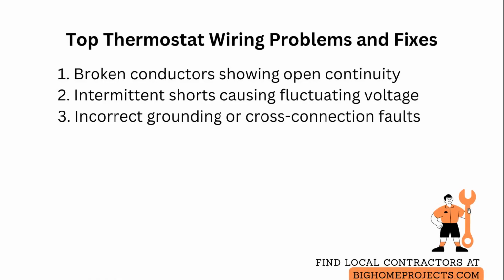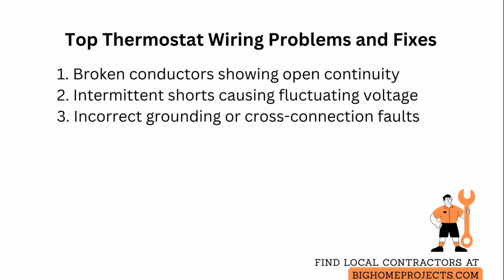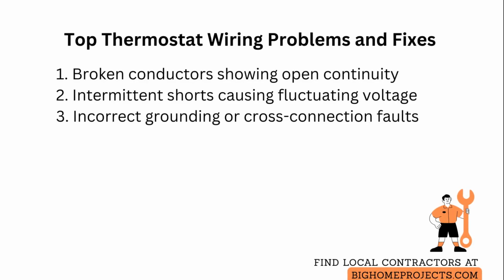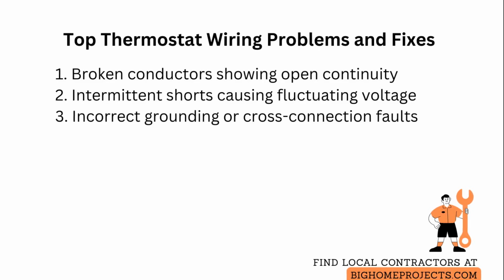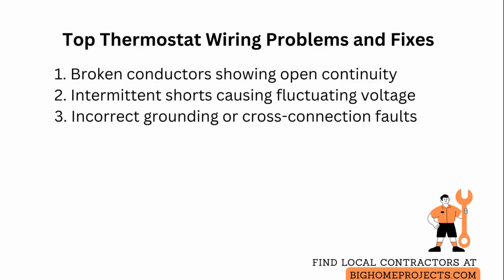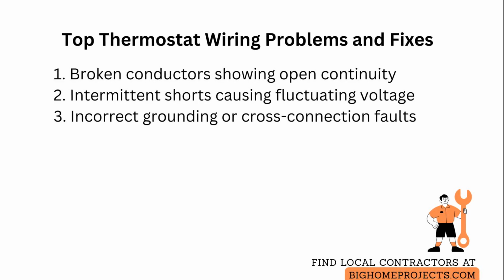For fluctuating voltage, isolate the section by testing at intermediate points, replace damaged cable segments, and secure wiring away from moving parts and sharp edges that cause wear. For grounding or cross-connection faults, trace and separate bundled cables, correct terminal wiring per the schematic, and if necessary, install a dedicated common conductor from the transformer to the thermostat.